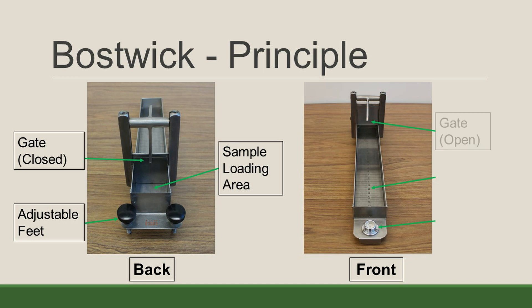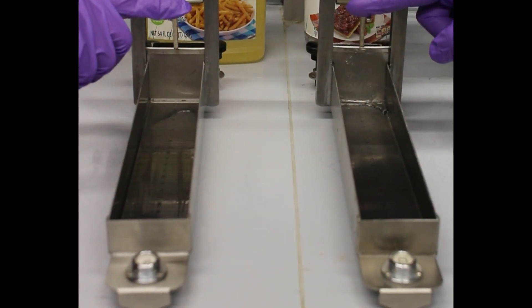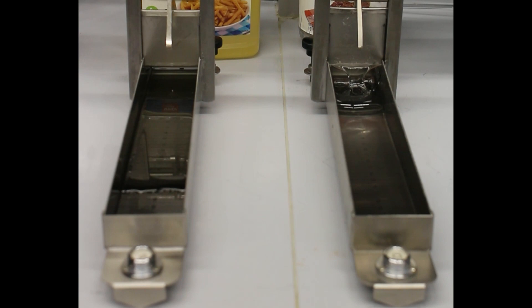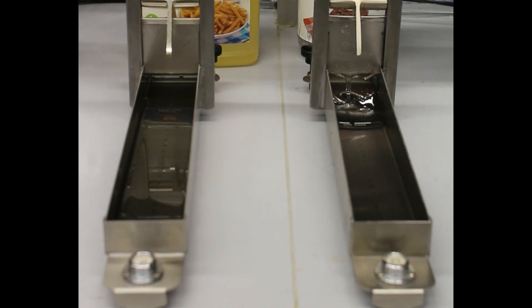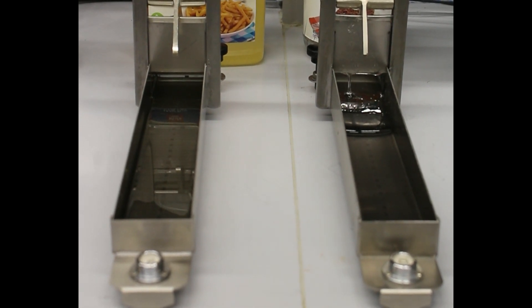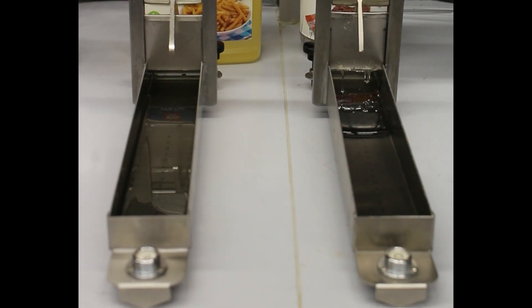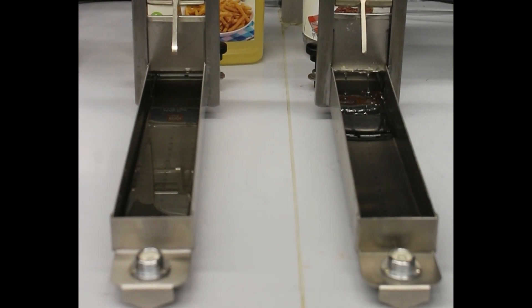In the front you have the gate now open in this picture, and the flow canal which is graduated or has markings to determine how far the fluid flowed. And in the very front is a level to help set the slope. In our example we compared canola oil on the left and corn syrup on the right. As you can see, samples that are fluid-like but with higher viscosity like corn syrup or ketchup work better with the Bostwick.